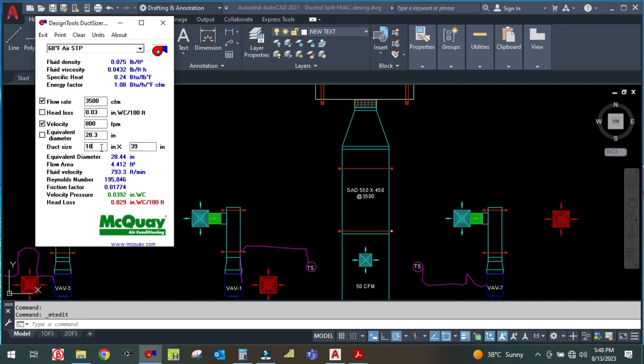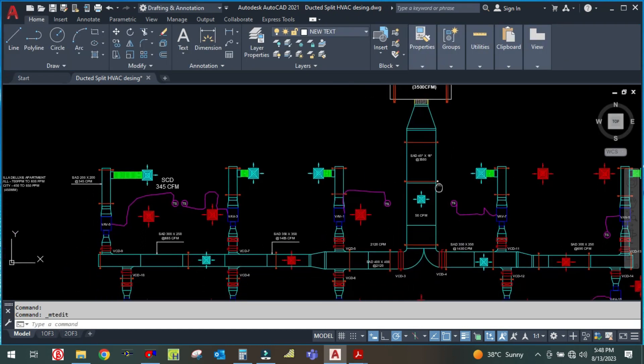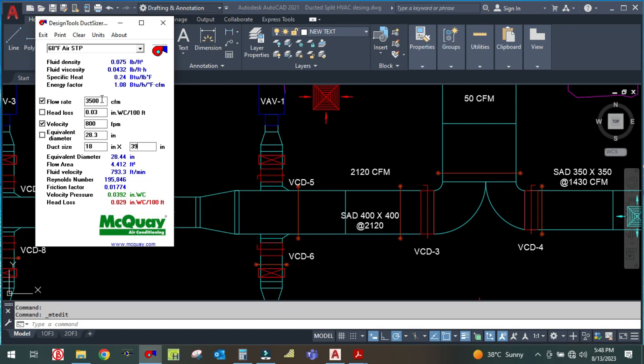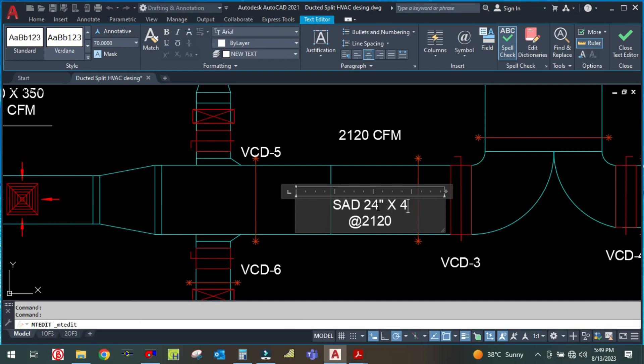Using the constant velocity method, I enter the duct height and I'm getting 40 inches wide. So the main duct is 40 inch by 18 inch at 3500 CFM. Similarly for this branch, do not change the velocity — just change the CFM to 2120, and with height 18 inch I'm getting 24 inch by 18 inch.